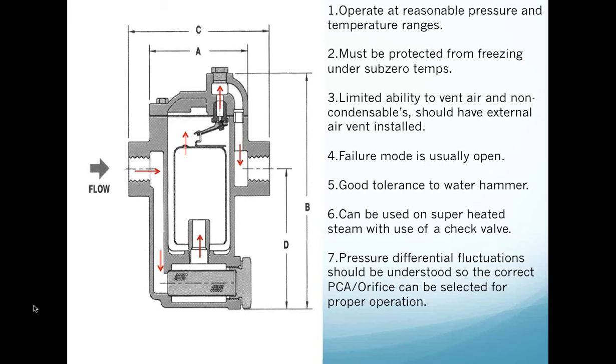I want to be able to get rid of the air and non-condensables so that I can fill the steam space with steam. One of the other things that I want to do, though, is make sure that I have vacuum breakers on my systems so that if and when a steam system goes down, whether it's intentional or unintentional, I can break the vacuum that will be formed when that takes place. And what that will do is act as a guardian for condensation-induced water hammer. So I'm always looking for safety-related issues, and vacuum breakers and air vents become safety-related issues.